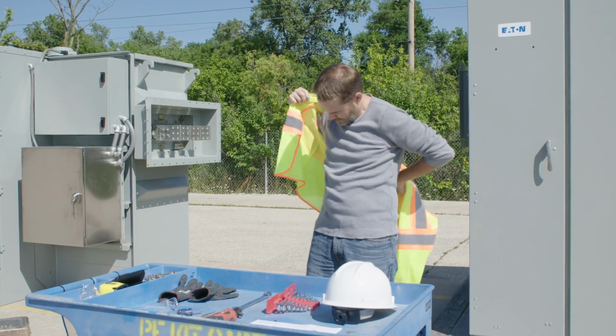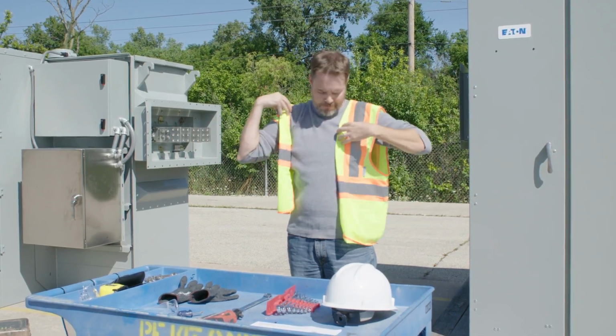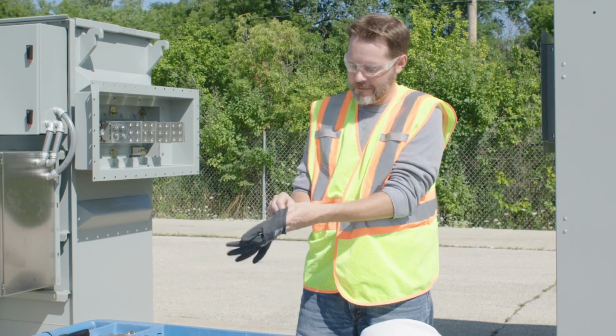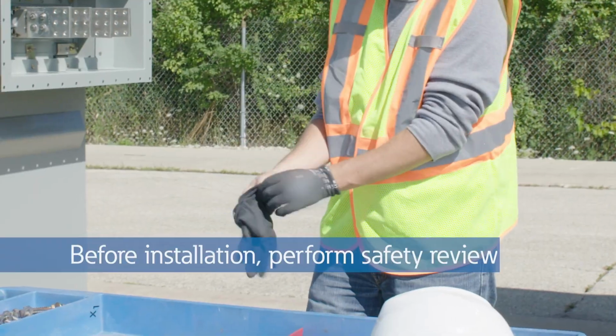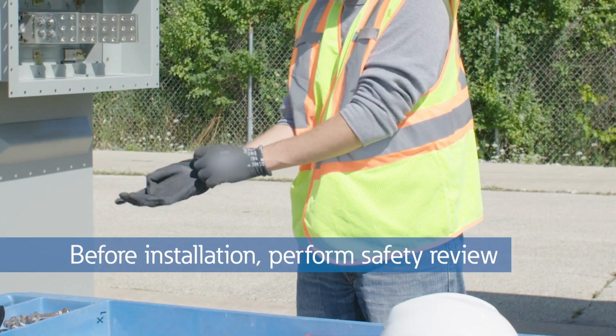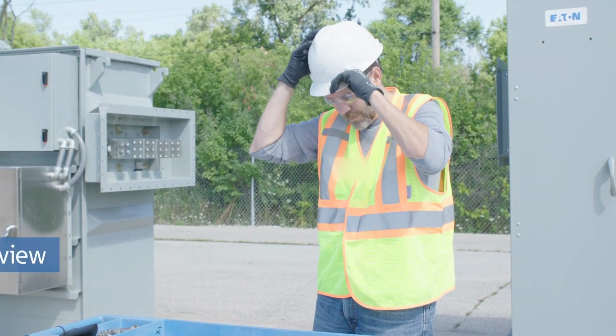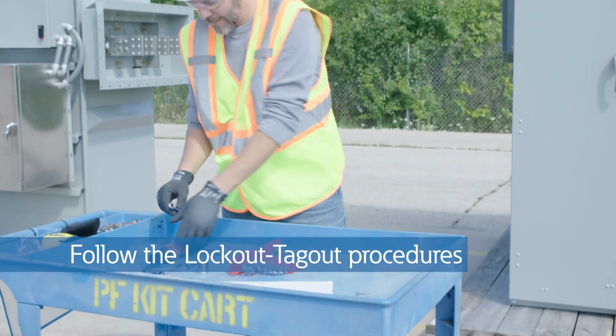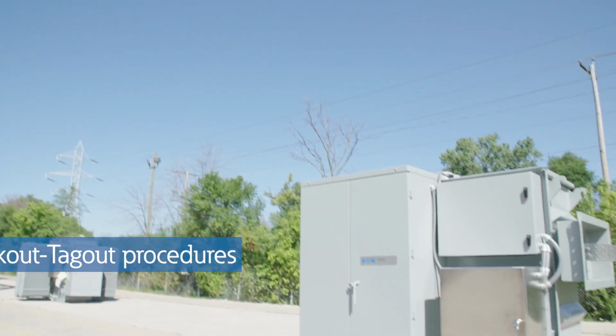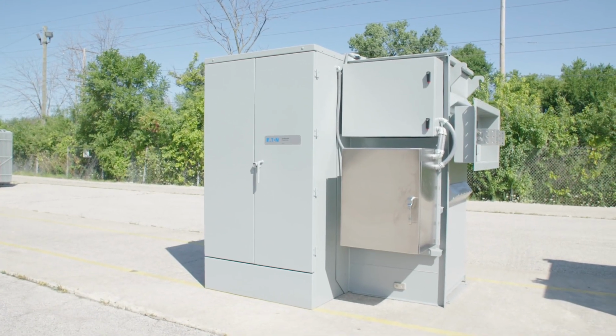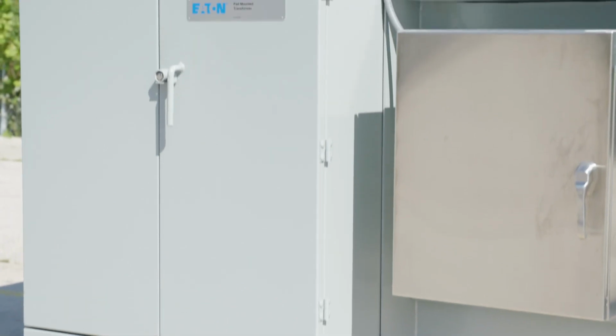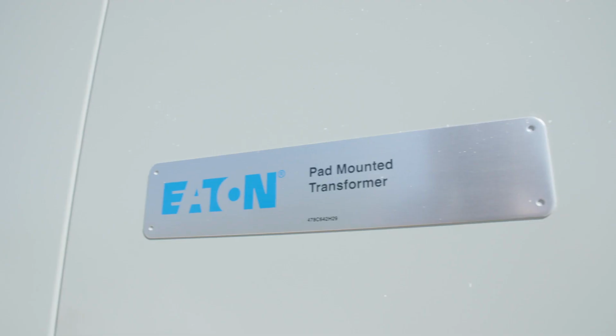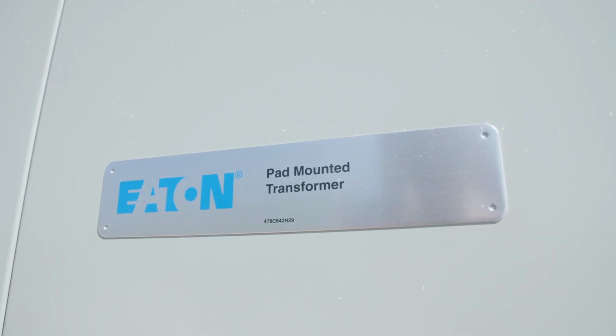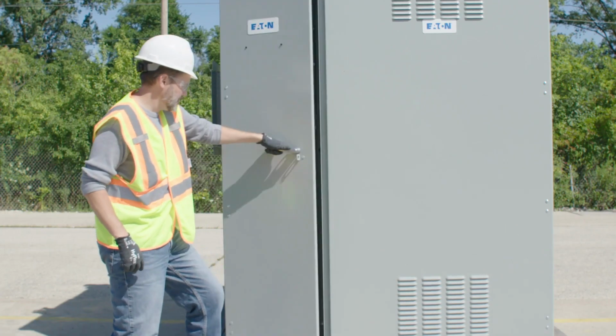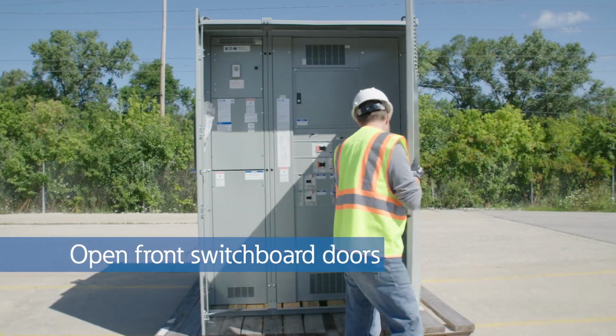Before starting the installation, make sure to perform a proper job and safety review. This includes ensuring the proper PPE gear is available for personal safety and protection, and follow the lockout-tagout procedures. For the purposes of this installation demonstration, the transformer has already been set into its final place, following the transformer lifting and handling instructions. To begin the installation, open the front switchboard doors.